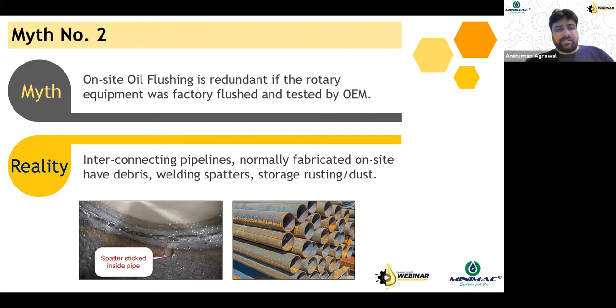So flushing was bypassed, it was not done properly, and later on they faced problems of debris coming off from the pipelines during the commissioning phase. So this myth actually can lead to a lot of damages during your commissioning activity, because the debris will come off and it would start collecting in your basket filters and strainers and so on and so forth.